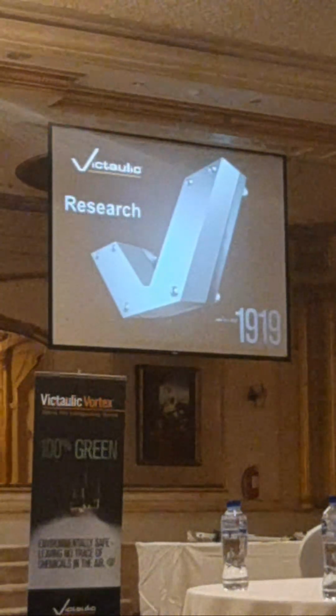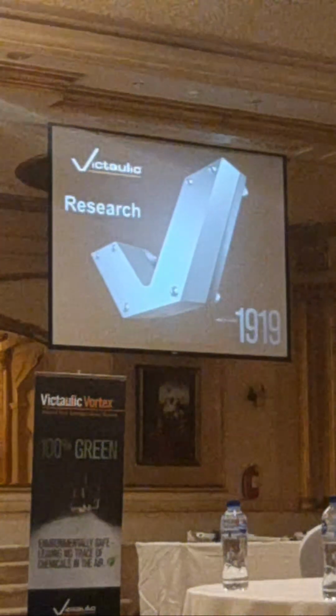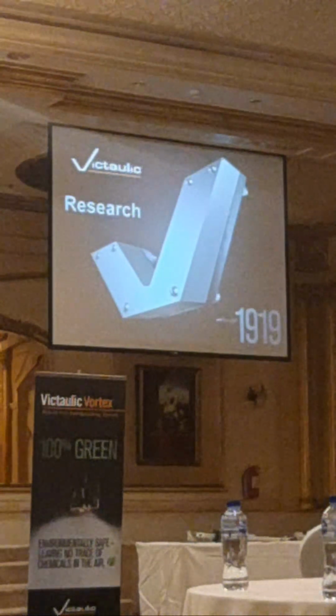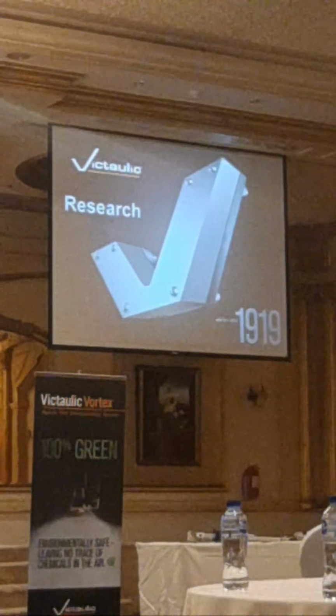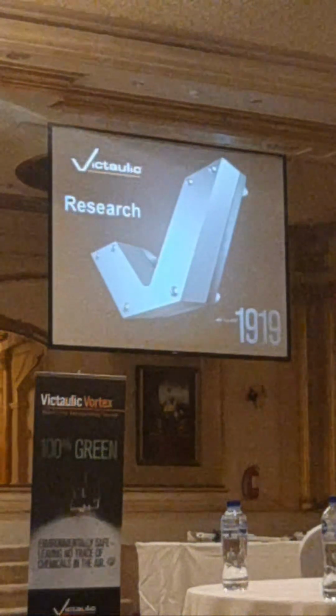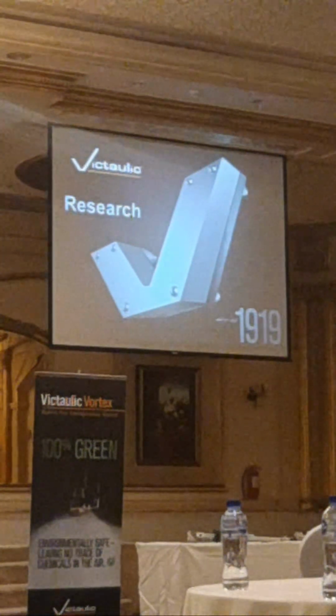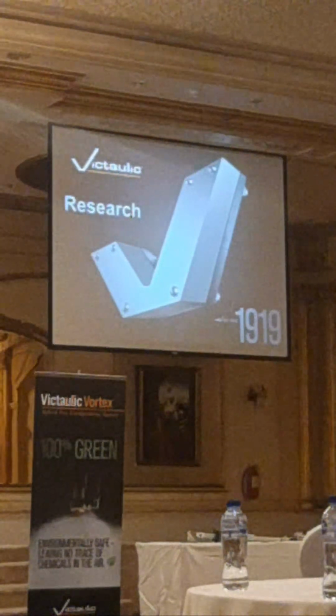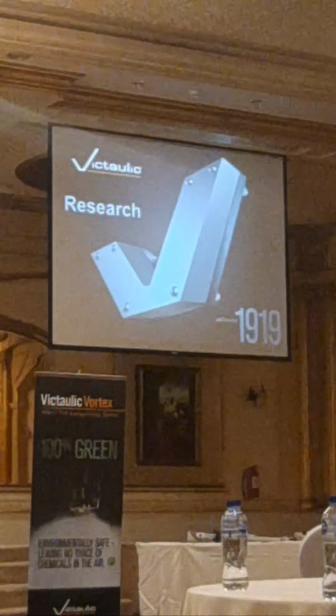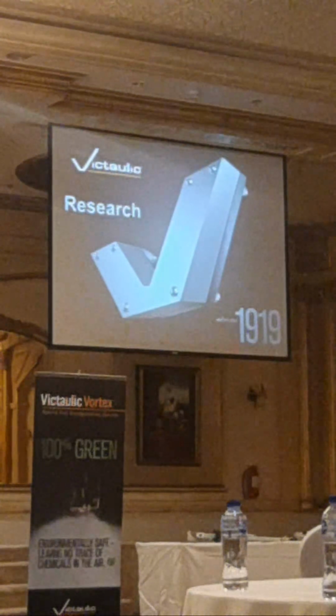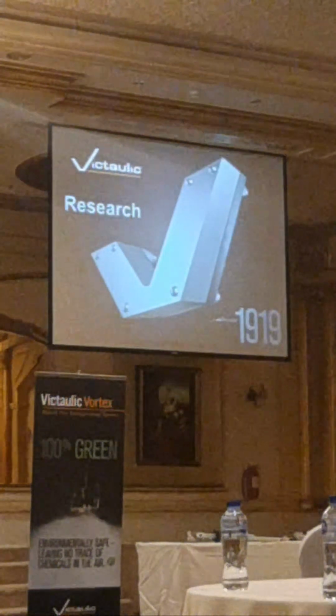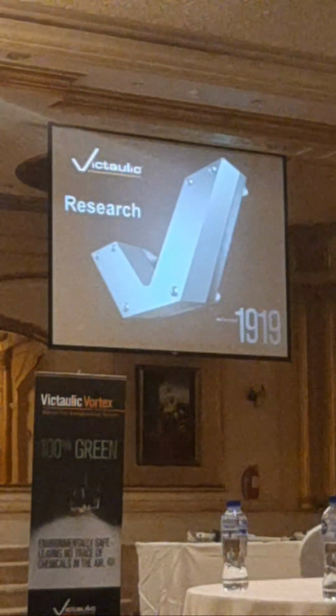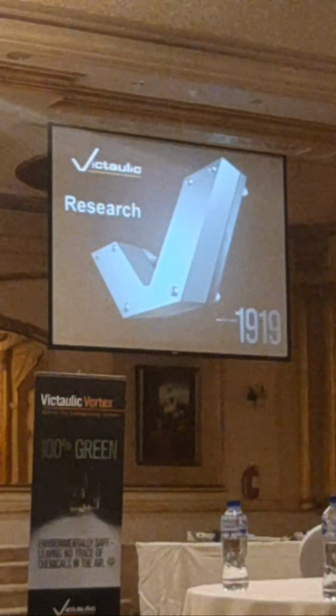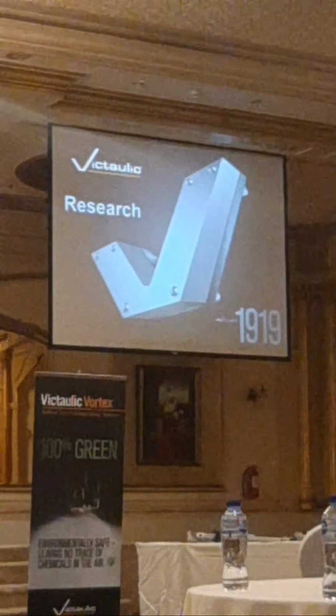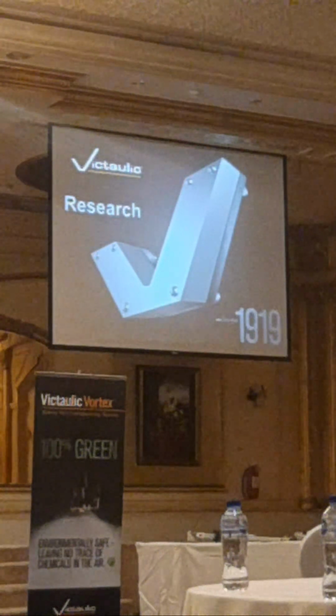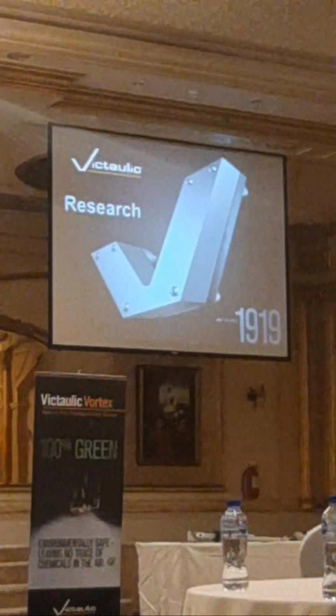When you're talking about the competition currently out there, you mentioned Aquasonic - there's also Sinorix from Siemens, which is more European. Both of them are more considered like a water mist system. The water droplets they have are going to be larger than the 10 micron that the Vortex system has, so that's already a big difference. In general we see that Tyco, Johnson Controls, or Siemens are not really focused as much on their hybrid part, but more on low pressure water mist.